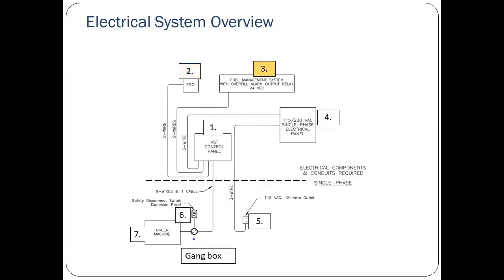The next system is 3, the tank gauge system, usually a Veeder-Root TLS 350 or 450. This system is sometimes called the tank sensor or the tank level sensor. In the event of an overfill, this system will send an alert to the VST control panel. The control panel will in turn deactivate the Green Machine. If the tank sensor system is not correctly connected to the control panel, then the Green Machine may ingest gasoline, which will ruin the vacuum pump inside.